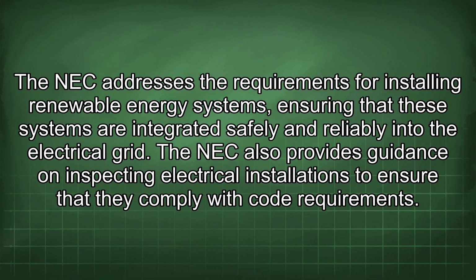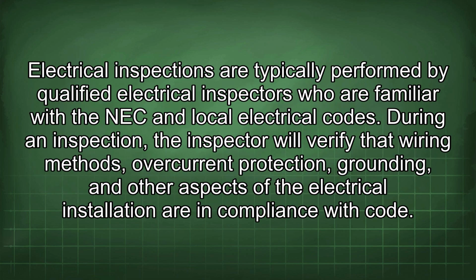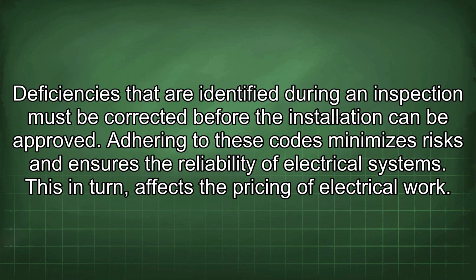The NEC also provides guidance on inspecting electrical installations to ensure that they comply with code requirements. Electrical inspections are typically performed by qualified electrical inspectors who are familiar with the NEC and local electrical codes. During an inspection, the inspector will verify that wiring methods, overcurrent protection, grounding, and other aspects of the electrical installation are in compliance with code. Deficiencies that are identified during an inspection must be corrected before the installation can be approved. Adhering to these codes minimizes risks and ensures the reliability of electrical systems.